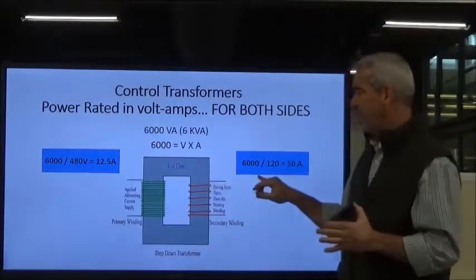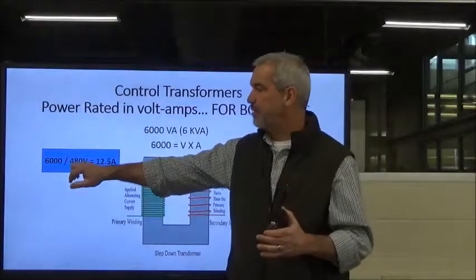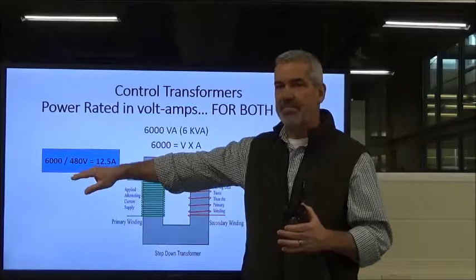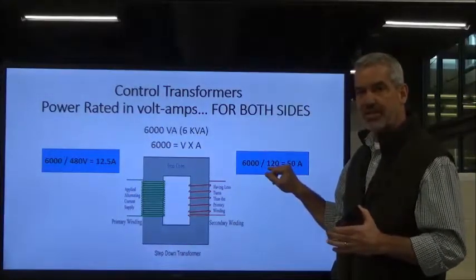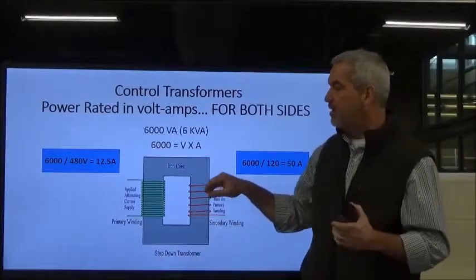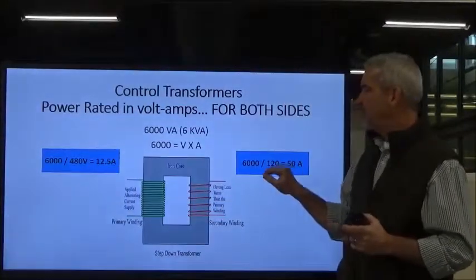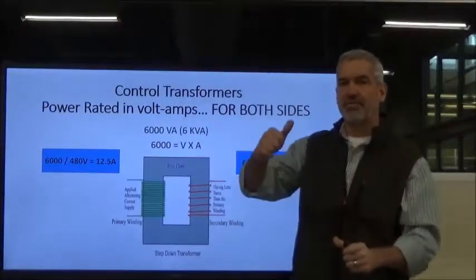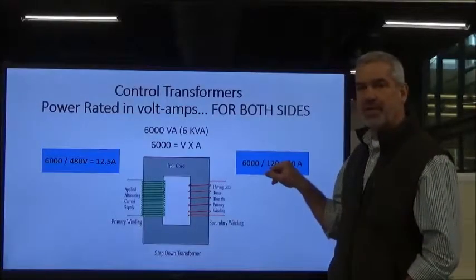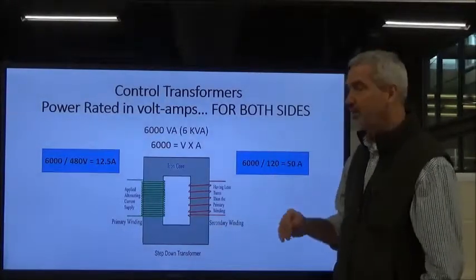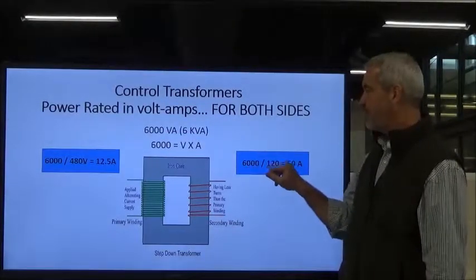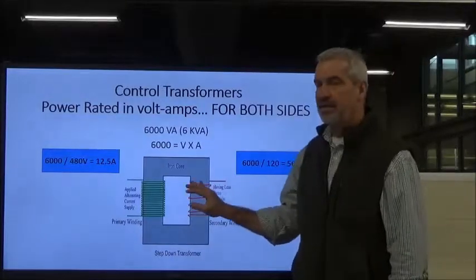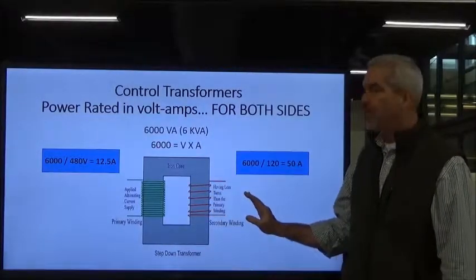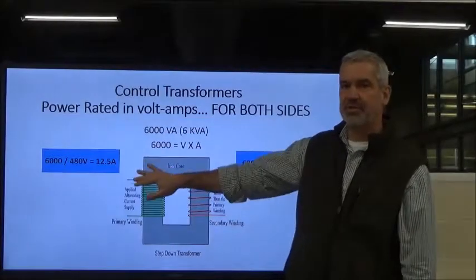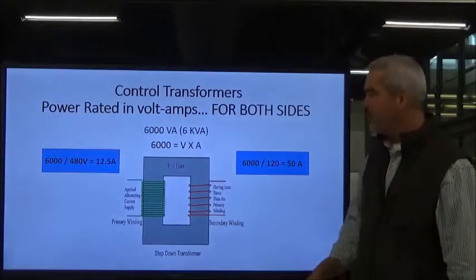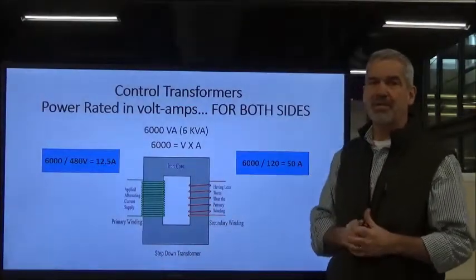So now we're on the secondary side. Let's say this is a 4-to-1 transformer. 480 volts, stepping it down by 4 gives us 120 volts on the secondary side. I'm going to show you the math behind that in a couple more slides. Now instead of 480 volts, we're producing 120 volts. Remember, voltage and current are inversely proportional, so I can't drop my voltage and have the amperage stay the same. The amperage is going to go up by 4 proportionally. So 6,000 volt amps divided by 120 means my secondary side is going to need to be rated for 50 amps. Regardless of the side, it's all a 6,000 volt amp or 6 kVA transformer. The difference will be the voltage, and that will determine the current that's pulled on that side.